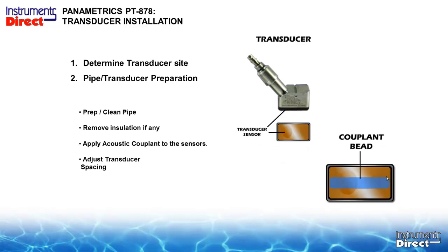Now we get to the transducer itself, and the most common question people ask me is, geez, how much goop do I put on the transducer? How much acoustic couplant do I put on the transducer? The rule of thumb is like toothpaste on a toothbrush, and the type of couplant that you use is also indicative of your application. Some of the GE kits standardize on using the water-soluble grease, which is great. You can clean up and wipe up, and your hands aren't too yucky when you're done. But it's not going to tolerate a moist application when you've got sweating pipes, or cold pipes, or hot pipes. Then you're going to have to use a silicone grease. So we have a host of different couplants you can use for different applications. Toothpaste on a toothbrush is usually all you need. The transducer is flat, the pipe is round.